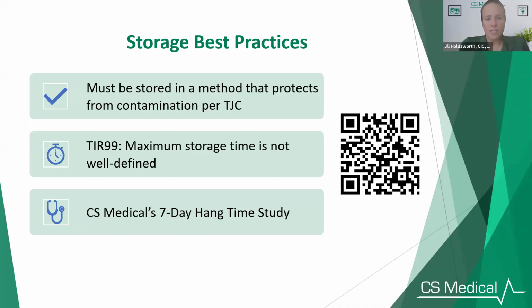So we did a study with our cabinets and then also a cabinet that didn't have HEPA filtered air. And we came to the conclusion that 7 days is really about the maximum that you can keep things hanging before they need to be reprocessed, because you are going to be opening that door over and over. So read the study, see what you think. But really, a risk assessment that shows why you chose what you did is what you're going to need to do. Next slide.